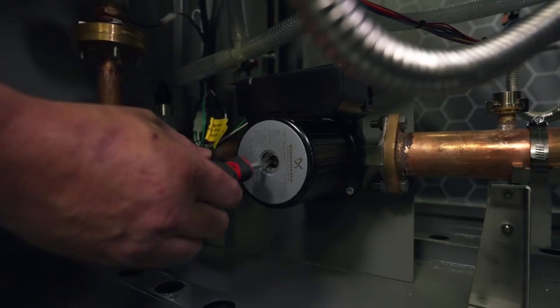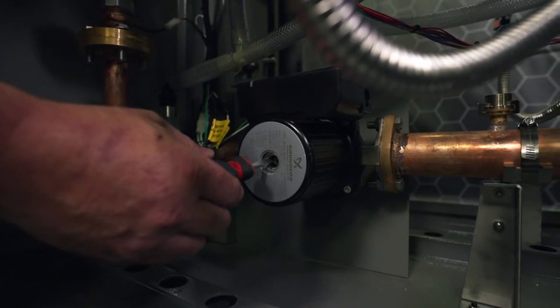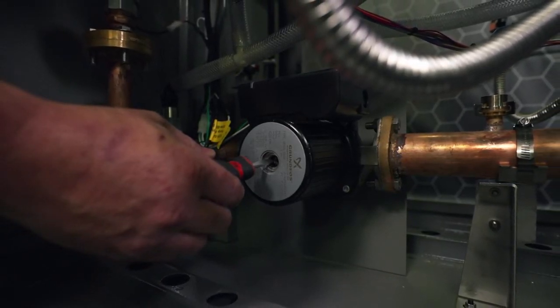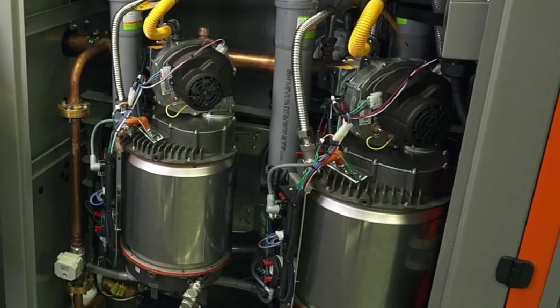Then use the flathead screwdriver to manually turn the shaft towards the direction of flow. Turn the shaft until it is easy to turn. This will unseize the pump.